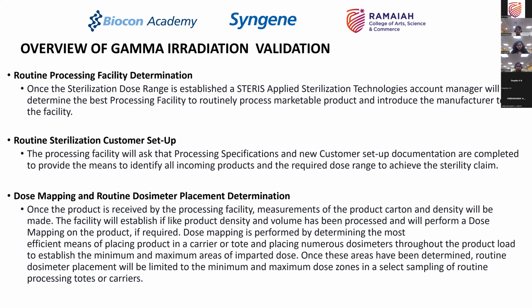There could be more than one minimum spot or more than one maximum dose area. So you will place only a limited number of dosimeters during the routine process. But during the mapping, you will place them throughout the load and make sure that you identify the penetration correctly. So this is an important exercise.